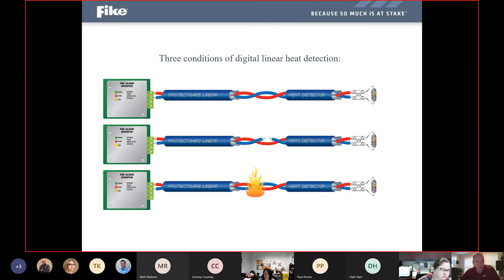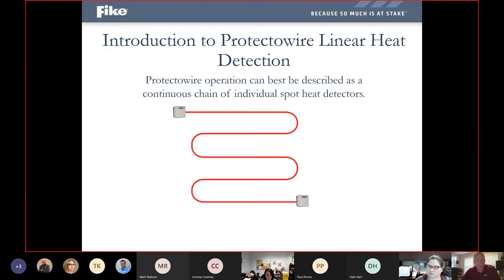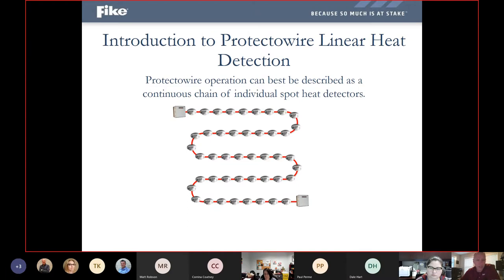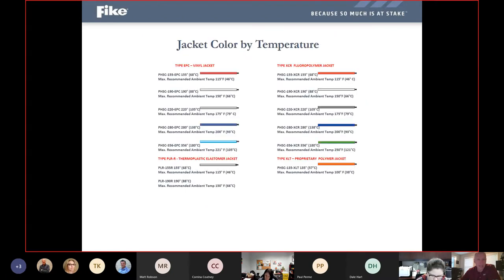But at the same time, when it sends that signal out to confirm the temperature, if it sees that, hey, my wire was set at 150 degrees and I'm reading 150 degrees, so this is a fire. Now let's trigger an alarm. It's not just a trouble condition, it's an alarm. So it confirms the temperature and sets the system into alarm. And so with that Protectowire, it can best be described as a continuous chain of individual spot heat detectors, because anywhere along that wire that short or that temperature increase occurs, the system will respond to it and detect it.